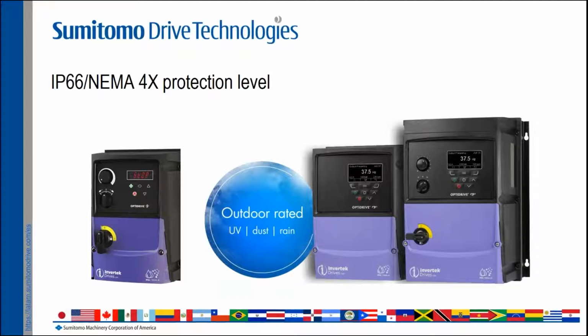And of course, I want to point out that all the Invertek drives have a variant with a certain IP level of protection. Some of them are outdoor rated, so they also have a NEMA 4X certification, so they are protected against corrosion also, so you can install them outdoors.